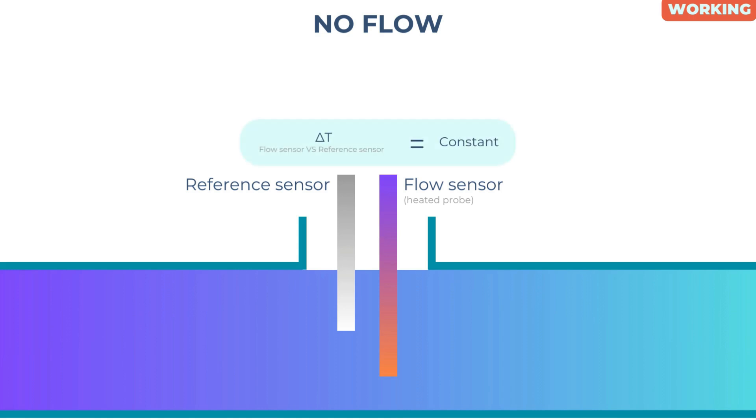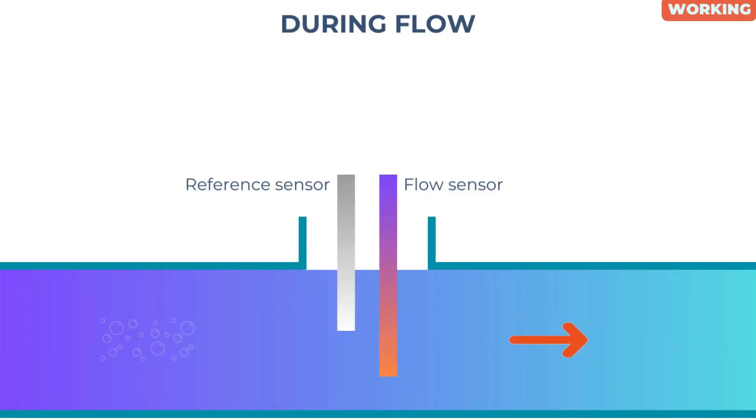During gas flow, the gas molecules transport heat away from the flow sensor and as a result the sensor cools and energy is lost. The circuit balance disrupts and the temperature difference between the flow sensor and the reference sensor changes immediately.